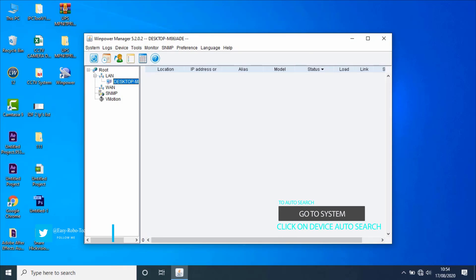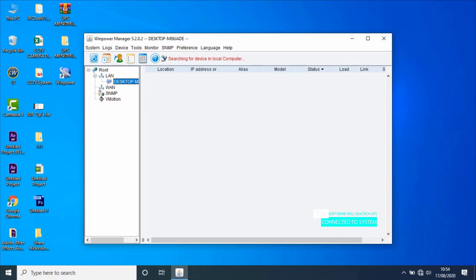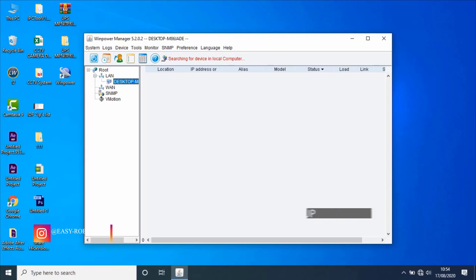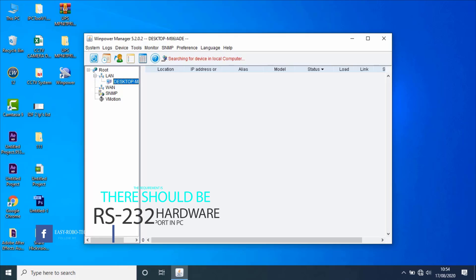To do that, go to System from the main menu, then click on auto-search device. The software starts searching for UPS connected to the system via USB and sets up communication between the software and UPS. Software can search for all UPS connected to the communication ports, and communicates with UPS via COM port. The requirement is that there should be an RS-232 hardware port or RS-232 virtual port in the computer.